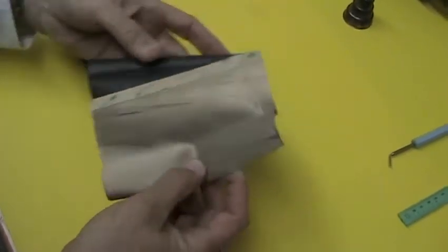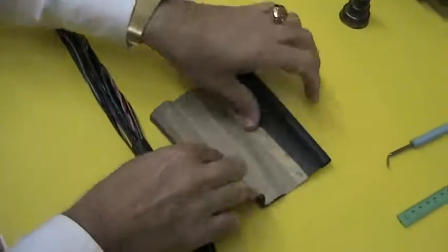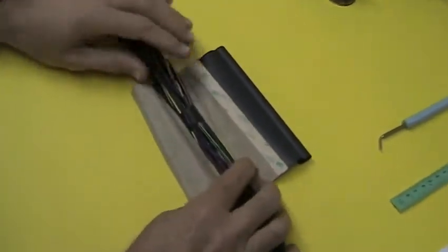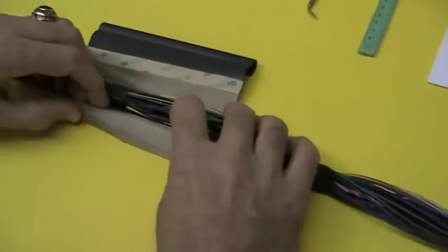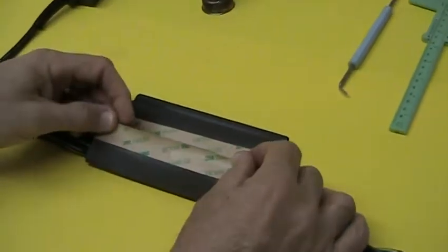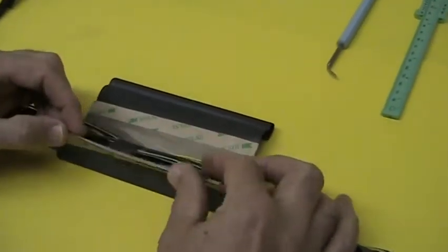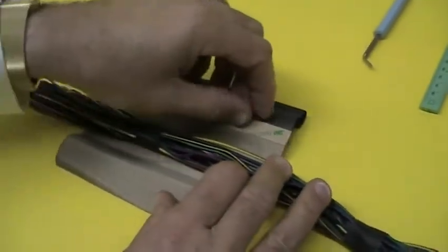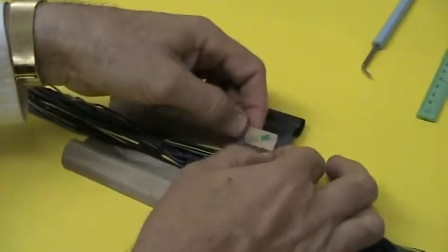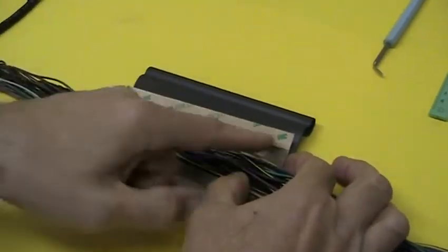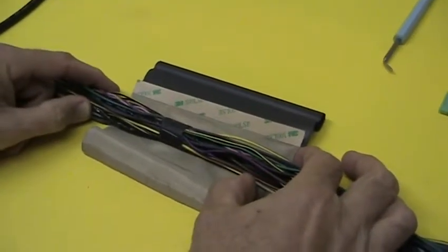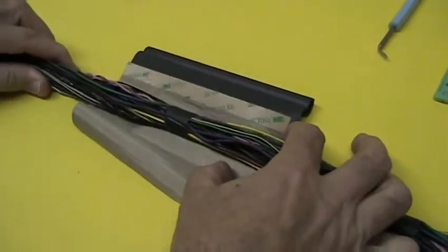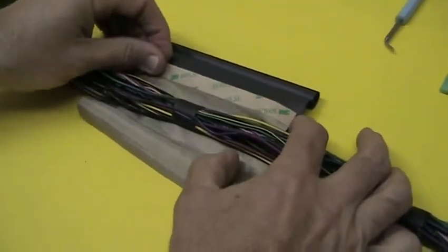To make the installation, you install your cable inside the shield. The heat shrinkable tubing will be on the outside, the shield will be facing up. What you want to see is along the inside edge of the metalized shielding fabric is another strip of adhesive. Now I've already sized this tubing, this cable is roughly three quarters to seven eighths of an inch in diameter.